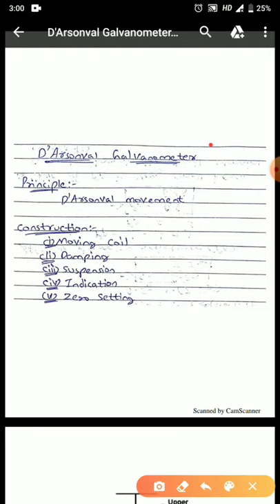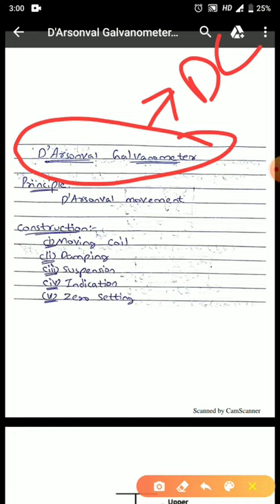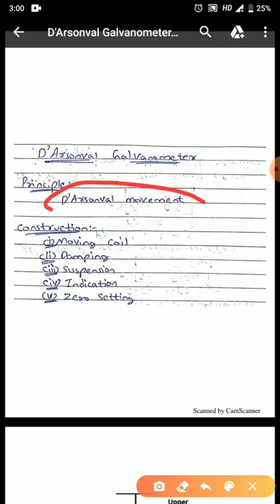Let us start with the discussion of D'Arsonval galvanometer. It is used when the supply is DC. The working principle of D'Arsonval galvanometer is called D'Arsonval movement. D'Arsonval movement is: if we have a permanent magnet and in between this permanent magnet we keep a coil, and through this coil we pass some current, this will make the coil a temporary magnet. This temporary magnet and the permanent magnet's flux will interact, causing movement in the coil — this is called D'Arsonval movement.